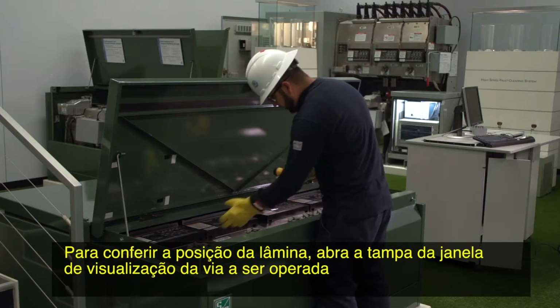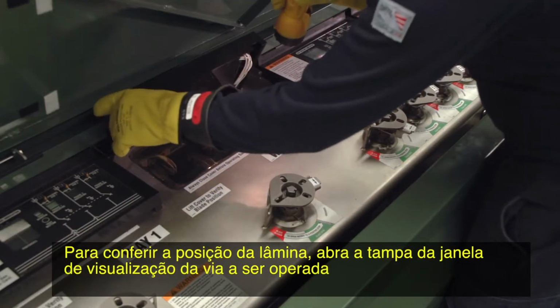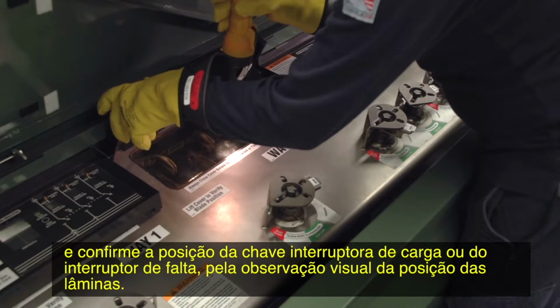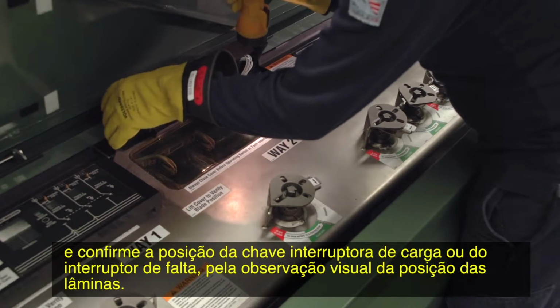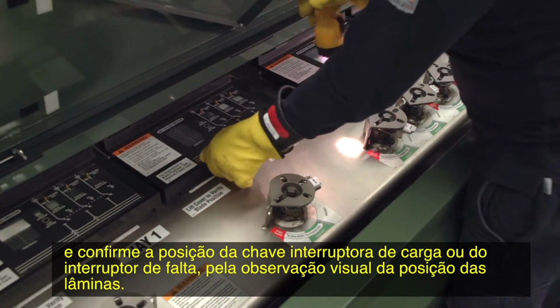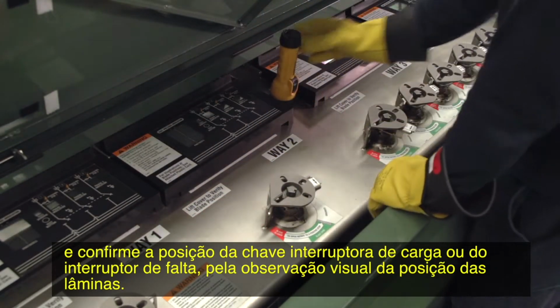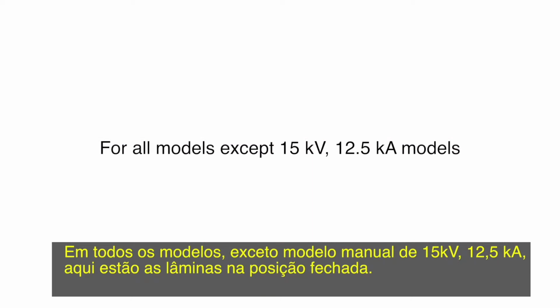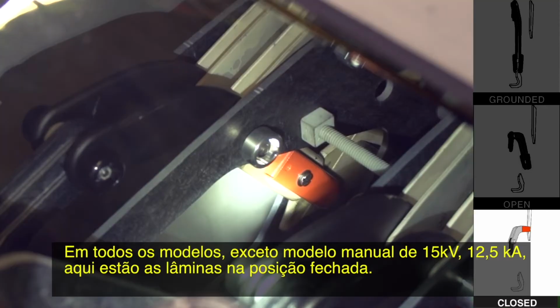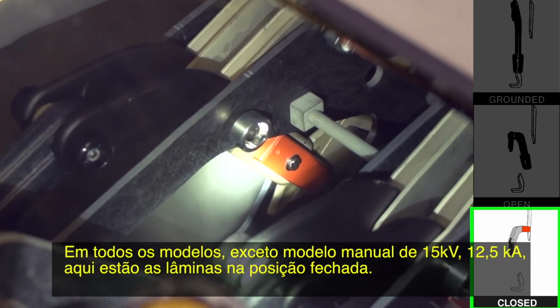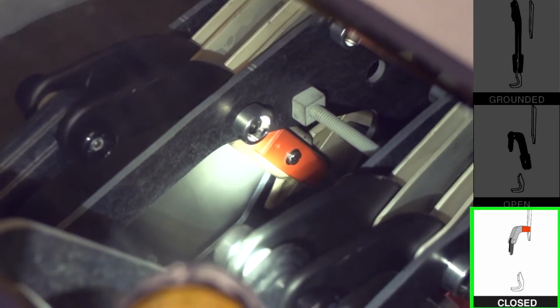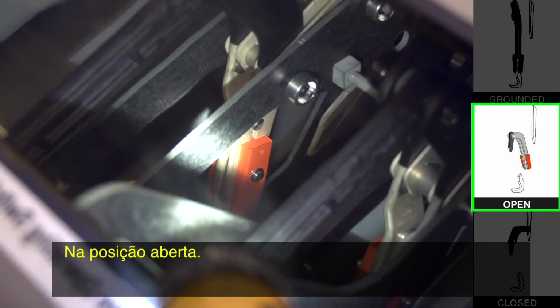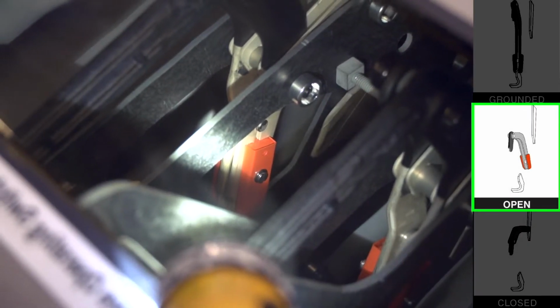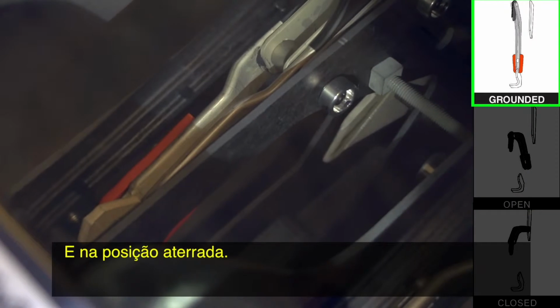To check the blade position, open the viewing window cover of the way you will operate and confirm the position of the load interrupter switch or fault interrupter by visually observing the position of the blades. For all models except manual 15 kV, 12.5 kA models, here are the blades in the closed position. The open position and the grounded position.